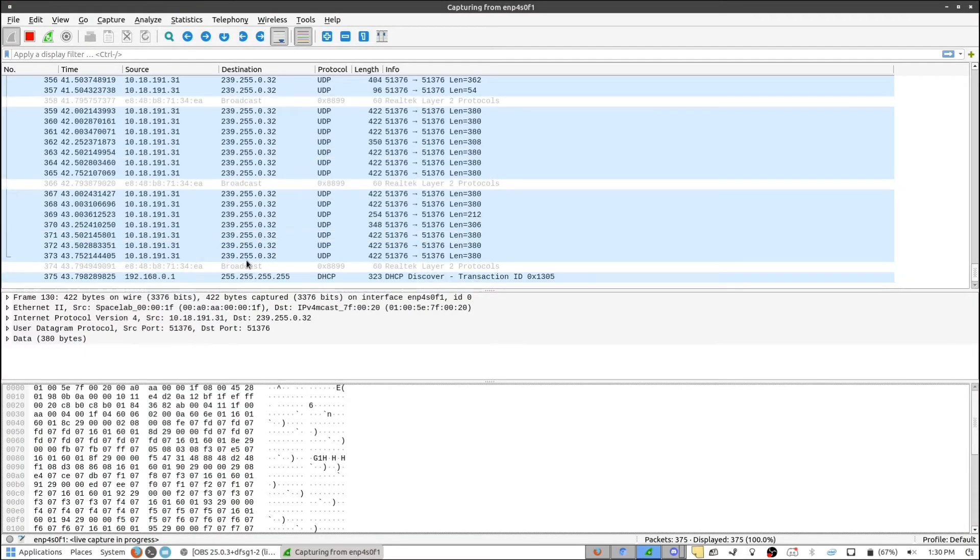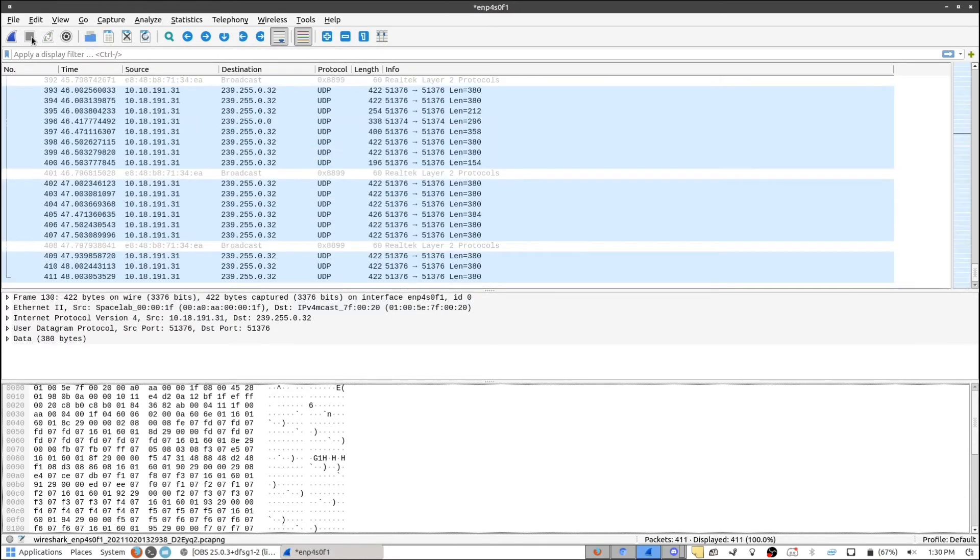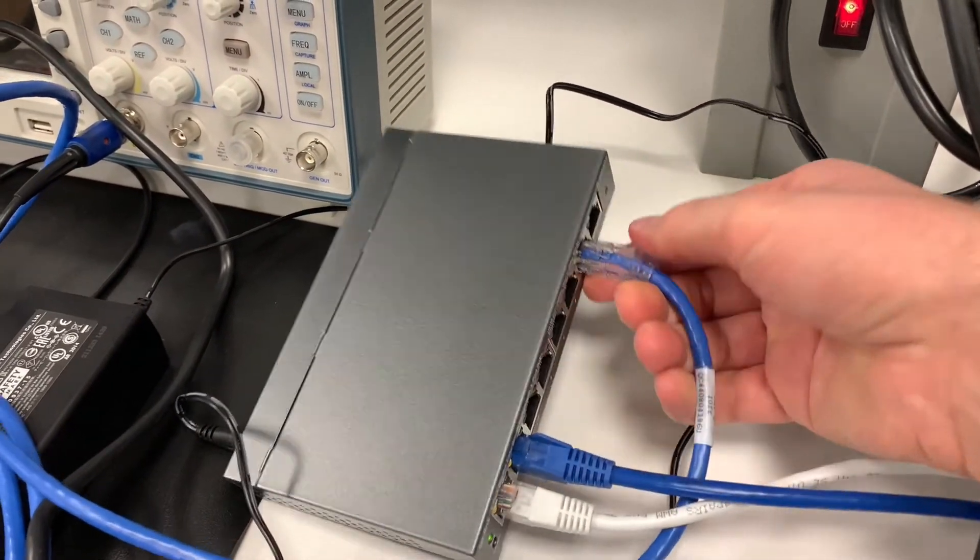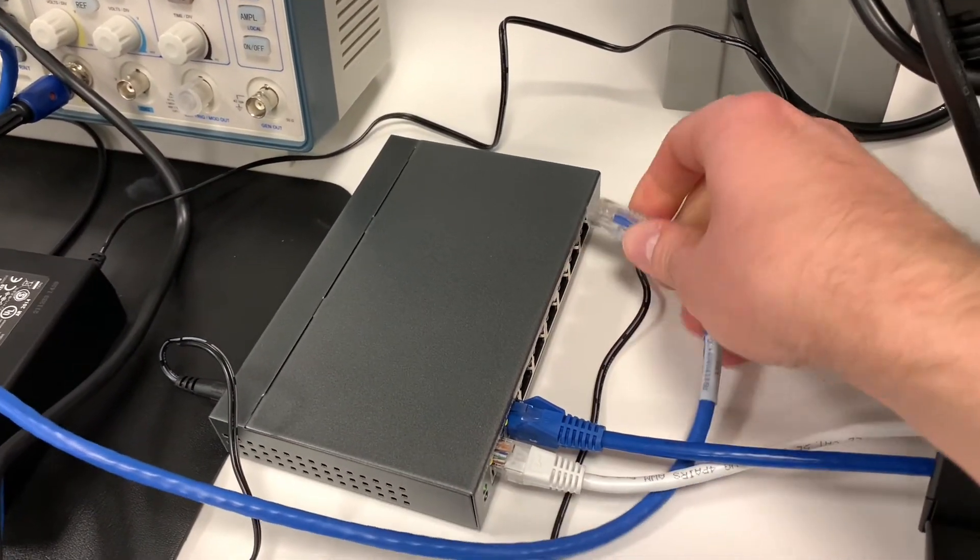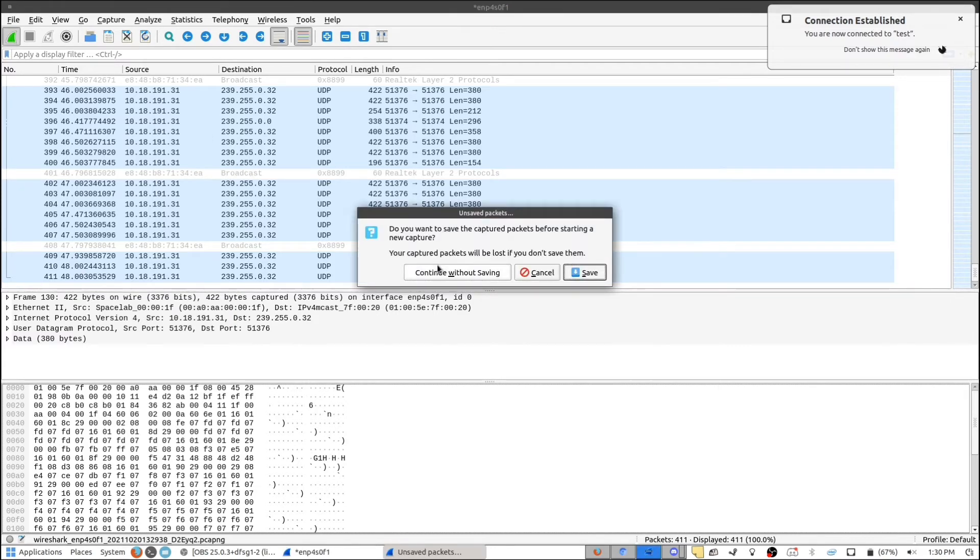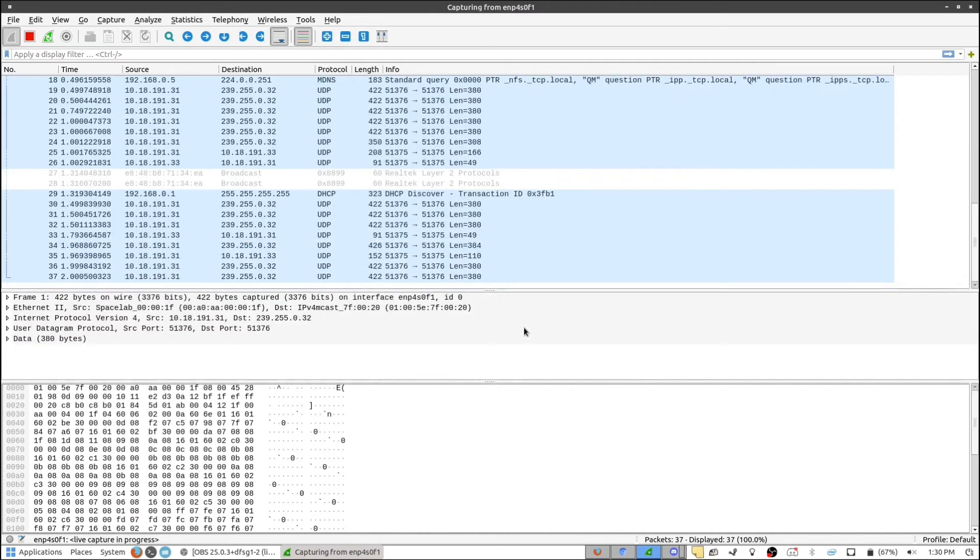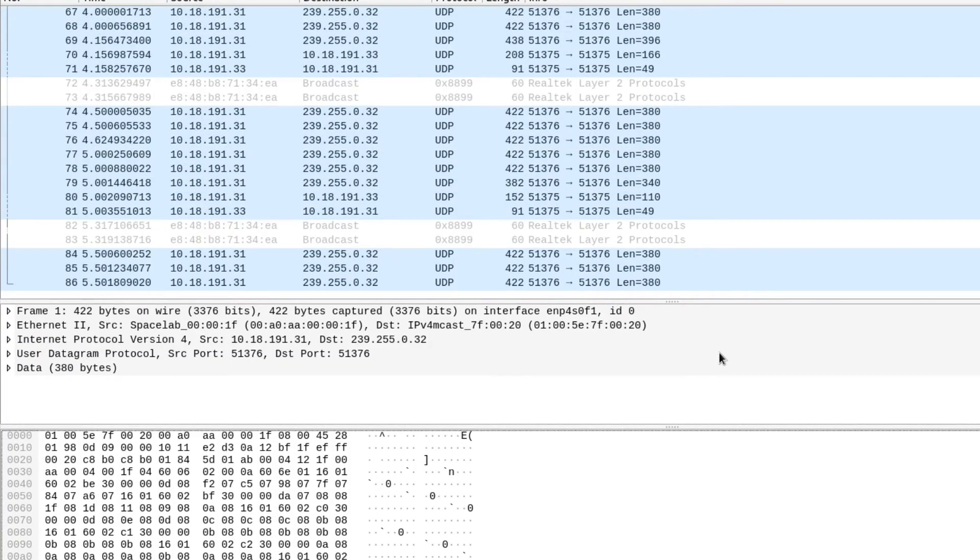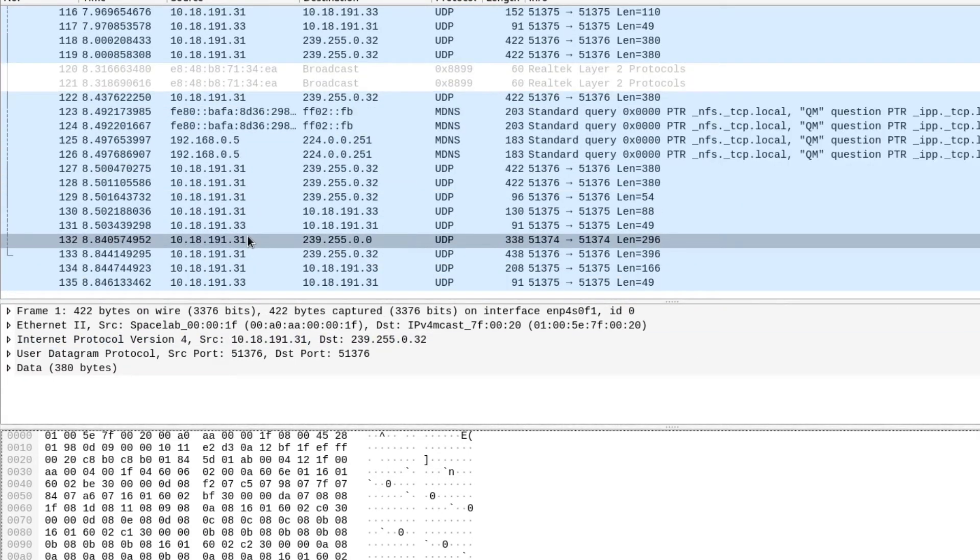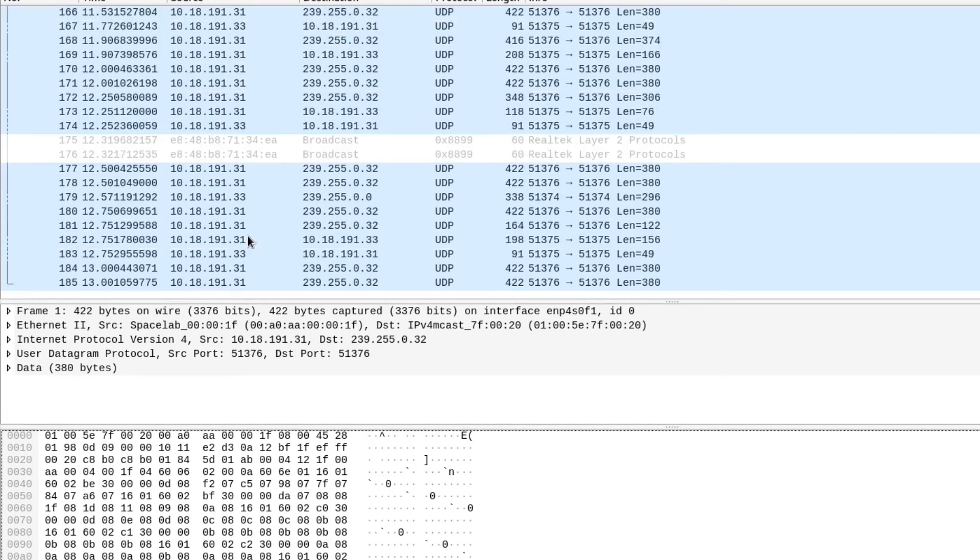So this is where our mirrored port comes in. What I'm going to do is first stop the capture. And on our switch here, I'm going to take my Ethernet cable out of port 7 and put it into port 8. And now that it's connected, I will make a new capture and we can take a look at what's going on. So now you might be able to see there's a lot more traffic going on, more so than before. And now we're seeing traffic from both ECGs number 33 and 31. So this is traffic going between the two.